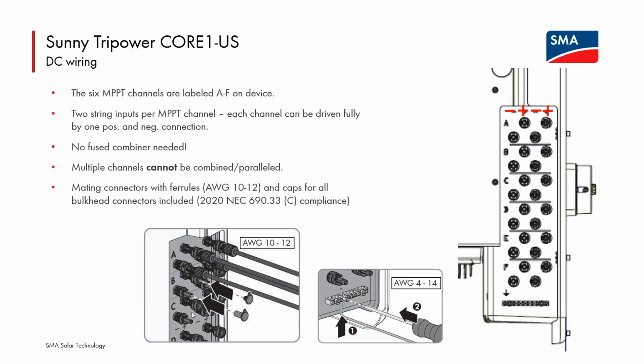Again, connection of the DC is fairly straightforward, home run conductors or sealing caps. The connectors and the ferrules that we include in the accessories bag for the CORE1 are for 10 or 12 gauge wire. You can source directly from Amphenol connectors for, I believe, at least 8 gauge, if not also 6. So if you are using a Y branch connector out at the array and bringing back a single positive and negative to drive one of the input channels and you've upsized the wire, again, what we're including in the accessories bag is appropriate for 10 or 12 gauge wires.